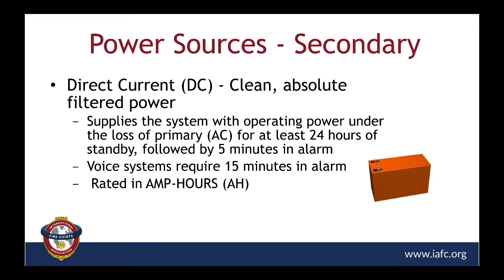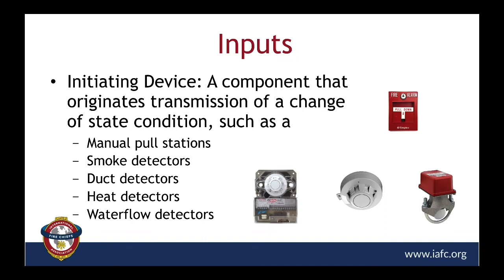So talking about the secondary power supply, it's usually supplied by batteries that are contained inside the control unit or in a separate battery cabinet. And they provide power for the operation of the system in the event that there is primary power failure. Now, the secondary power is required to have sufficient capacity to operate the system under a non-alarm condition for a minimum of 24 hours. And then at the end of that period, operate all of the notification appliances, such as the horns, bells, or strobe lights for 5 minutes in alarm. So this secondary power is very robust. Okay, next slide.